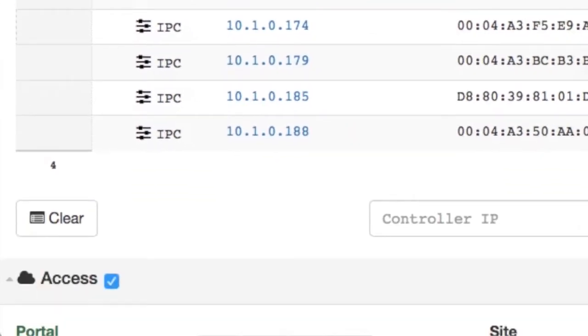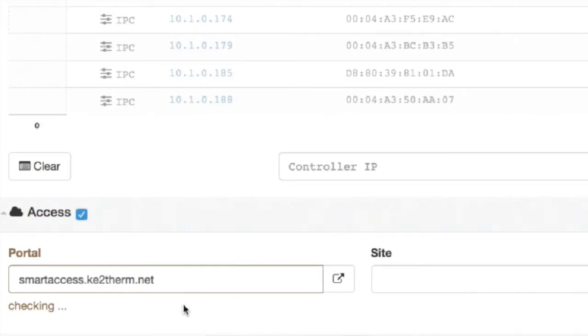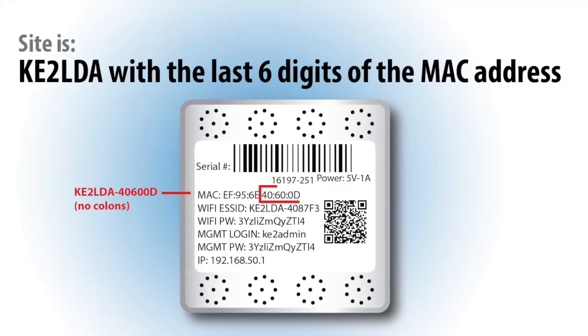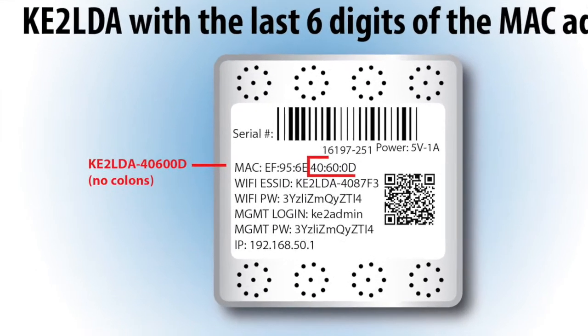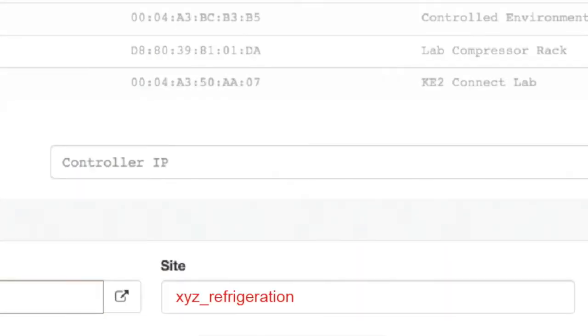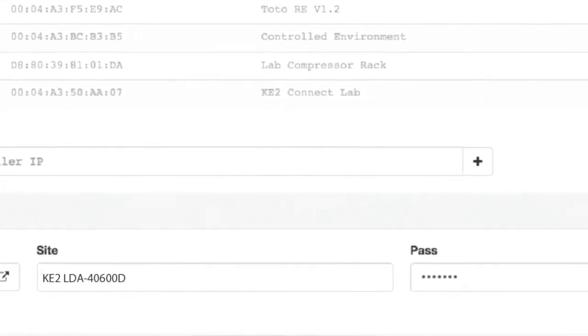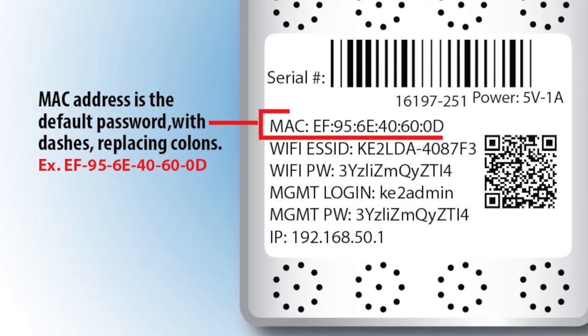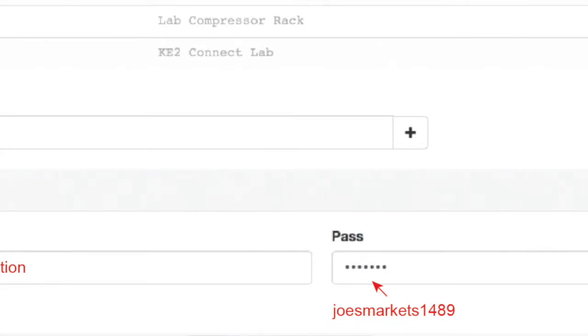Then select Access. From this screen, the portal is smartaccess.ke2therm.net and it will automatically populate the field — do not change this. In the site field, the default site is Key2 LDA combined with the last six digits of the LDA's MAC address. We recommend changing this for easier access in the future as well as for improved security. For the password, the default is the MAC address separated by dashes rather than colons. This should also be changed for security reasons.